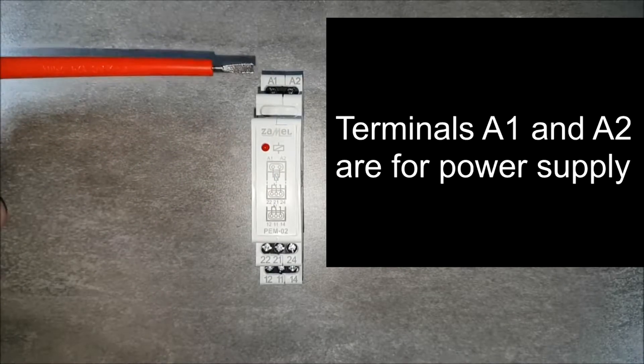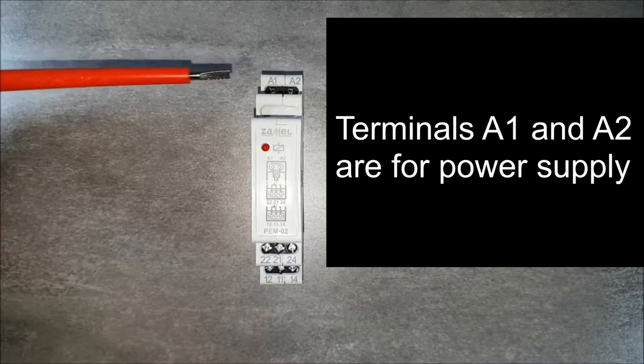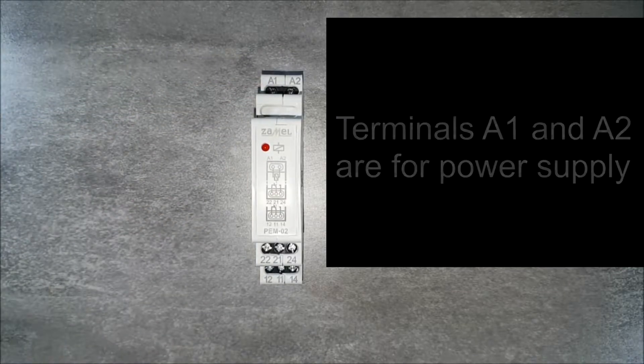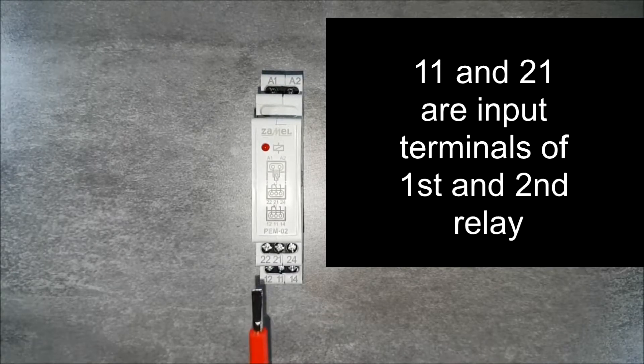PEM02 relay is powered by mains voltage. Supply voltage is connected to terminals A1 and A2, which are terminals of the relay coil. The relay contacts are located at the bottom of the device. They provide the output of two 16A relays, galvanically separated.